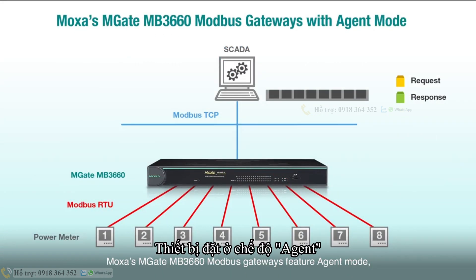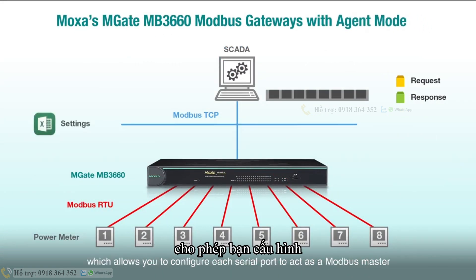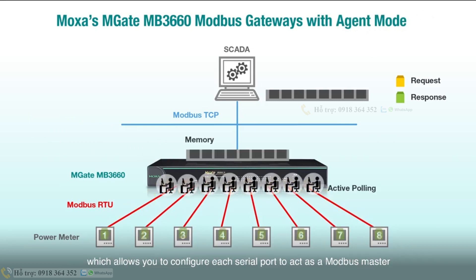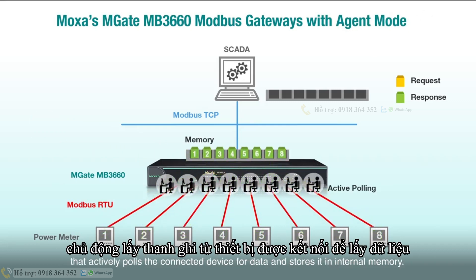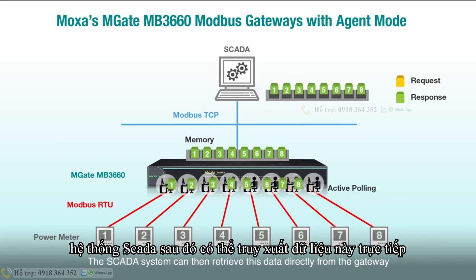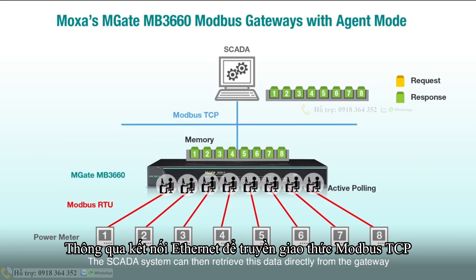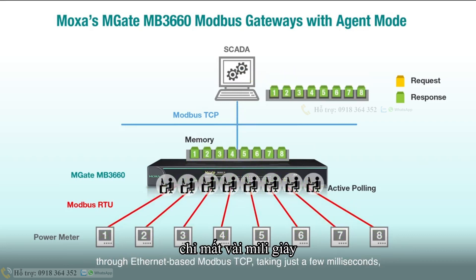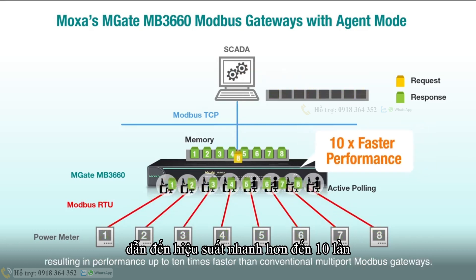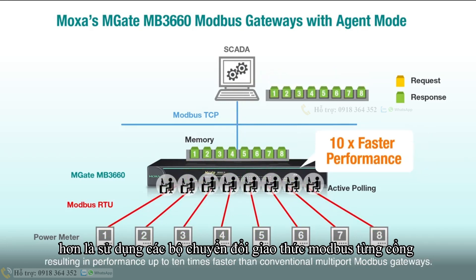Moxa's MB3660 Modbus gateways feature Agent mode, which allows you to configure each serial port to act as a Modbus master that actively polls the connected device for data and stores it in internal memory. The SCADA system can then retrieve this data directly from the gateway through Ethernet-based Modbus TCP, taking just a few milliseconds, resulting in performance up to 10 times faster than conventional multi-port Modbus gateways.